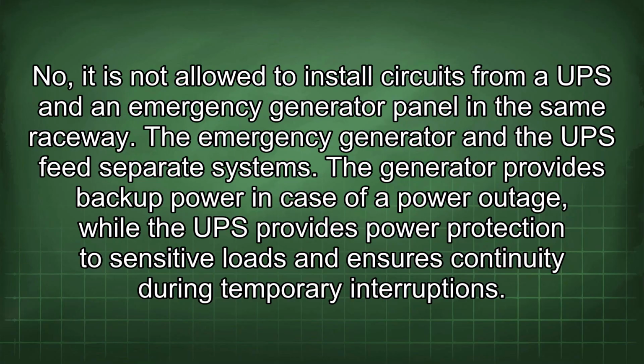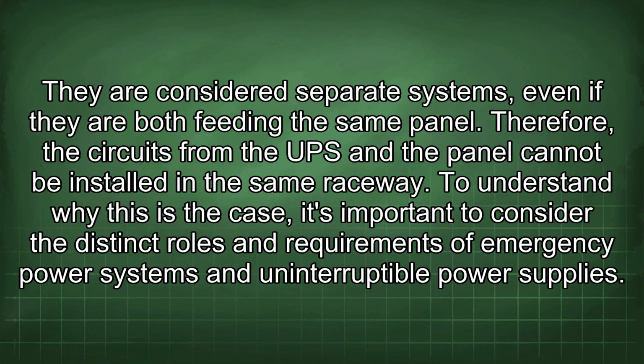No, it is not allowed to install circuits from a UPS and an emergency generator panel in the same raceway. The emergency generator and the UPS feed separate systems. The generator provides backup power in case of a power outage, while the UPS provides power protection to sensitive loads and ensures continuity during temporary interruptions. They are considered separate systems, even if they are both feeding the same panel. Therefore, the circuits from the UPS and the panel cannot be installed in the same raceway.